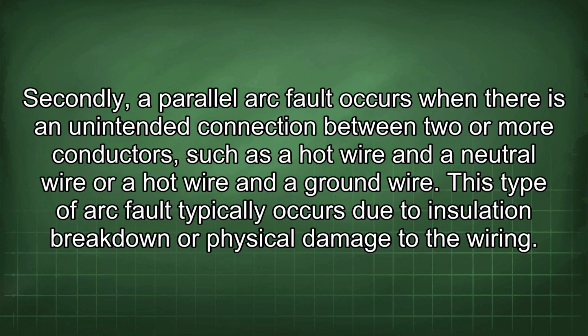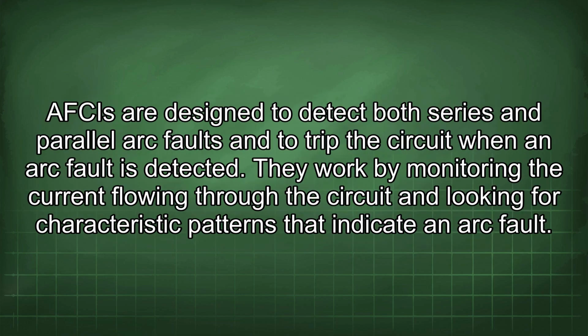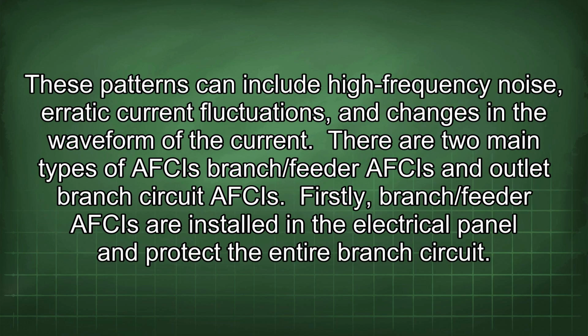Secondly, a parallel arc fault occurs when there is an unintended connection between two or more conductors, such as a hot wire and a neutral wire, or a hot wire and a ground wire. This type of arc fault typically occurs due to insulation breakdown or physical damage to the wiring. AFCIs are designed to detect both series and parallel arc faults and to trip the circuit when an arc fault is detected. They work by monitoring the current flowing through the circuit and looking for characteristic patterns that indicate an arc fault. These patterns can include high-frequency noise, erratic current fluctuations, and changes in the waveform of the current.